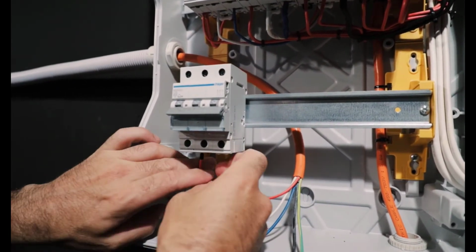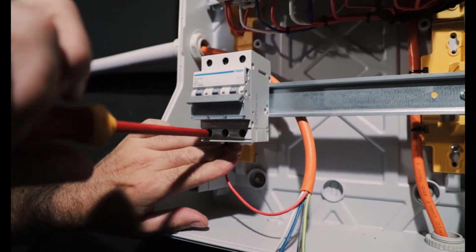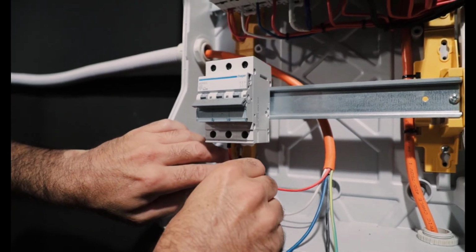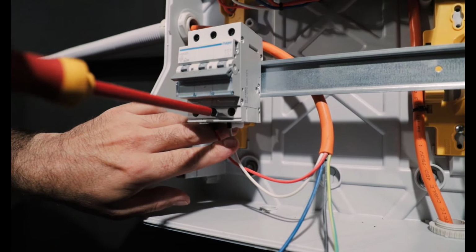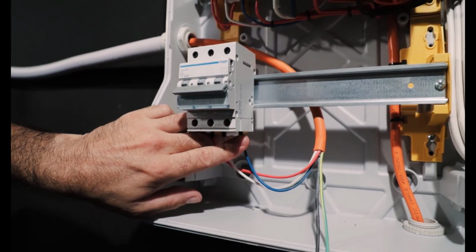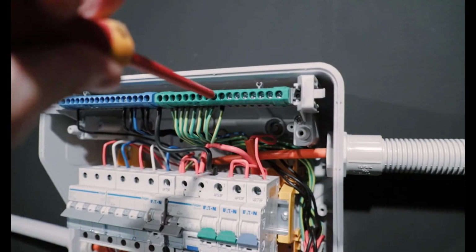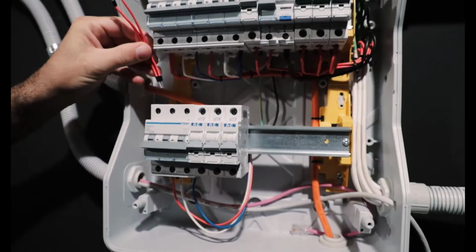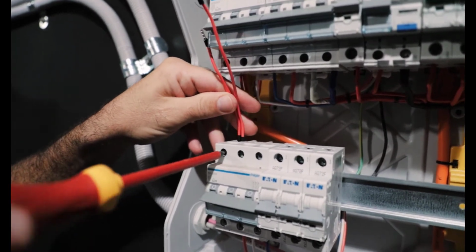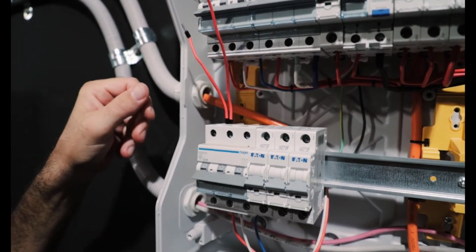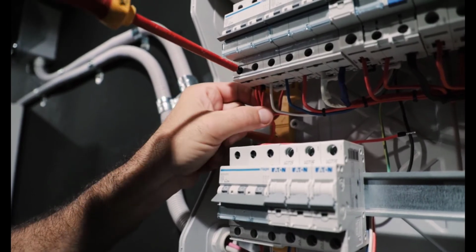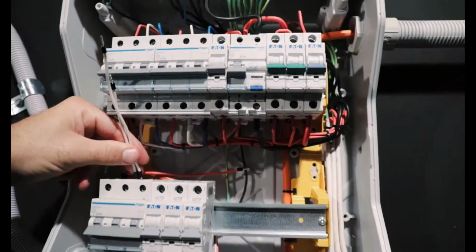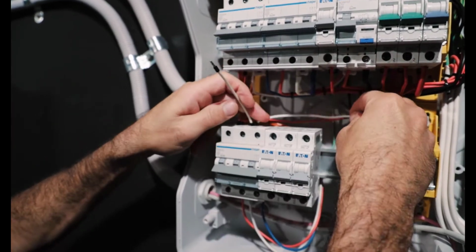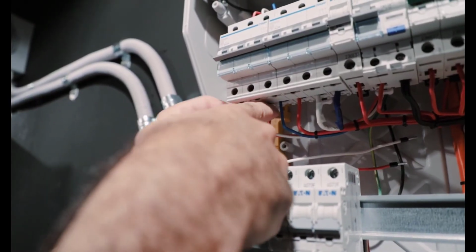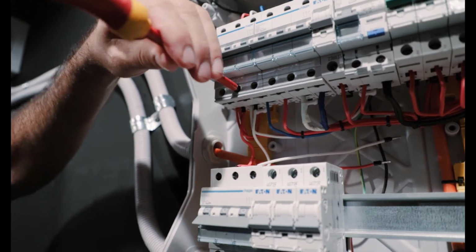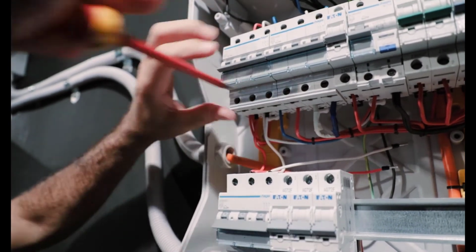Now we're going to wire in the 3-phase switch. Again, unfortunately the 3-phase switch is not included with the bill of materials for the Sonnen system, so you will need to supply that, and it does need to be a latched 3-phase isolator. And then we get in place earth and neutral. So now, just like before, the meter needs to have 3 separate single-phase MCBs. It is not a 3-phase load. Each phase of the meter can be disconnected and activated and deactivated separately for testing purposes and for functional purposes, so it does not need to be a latched 3-phase MCB. If anything, putting on a latched 3-phase MCB for the meter will cause more problems.